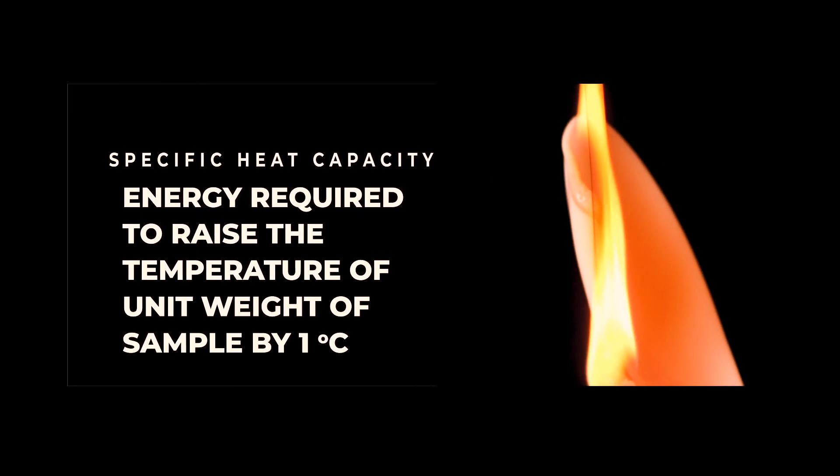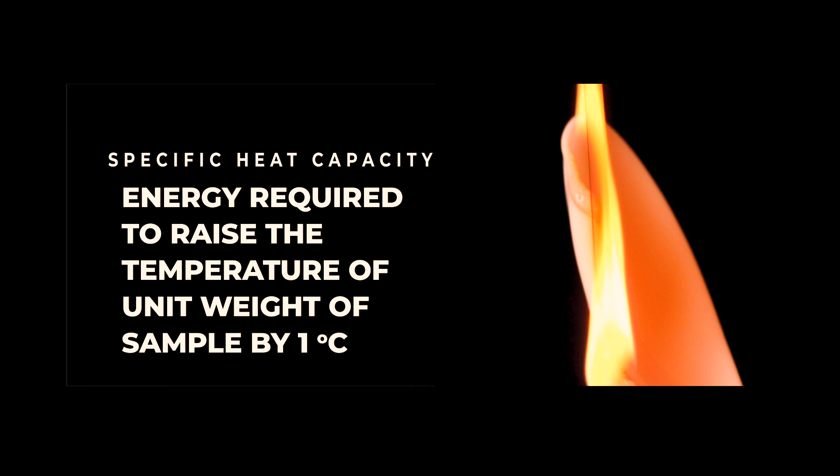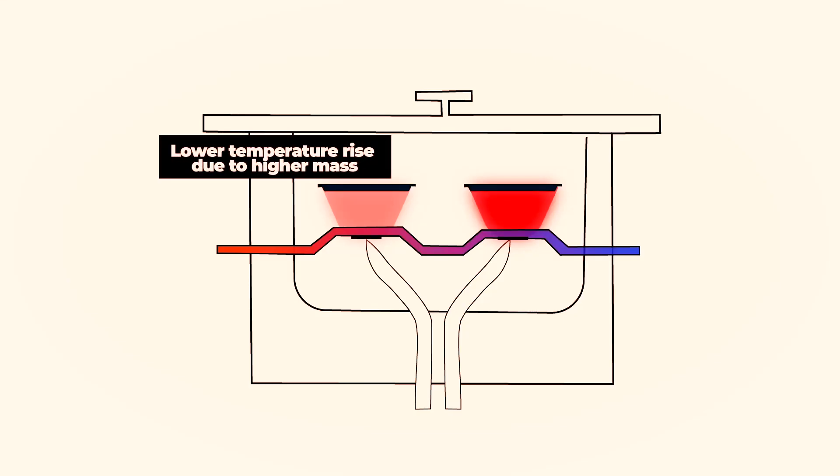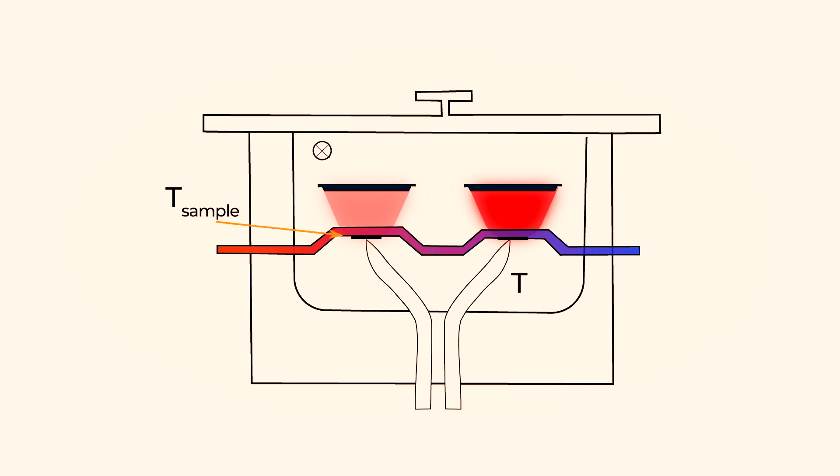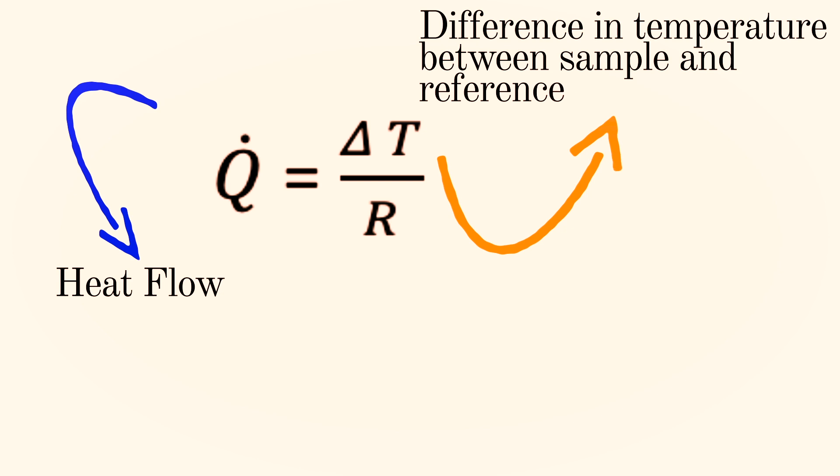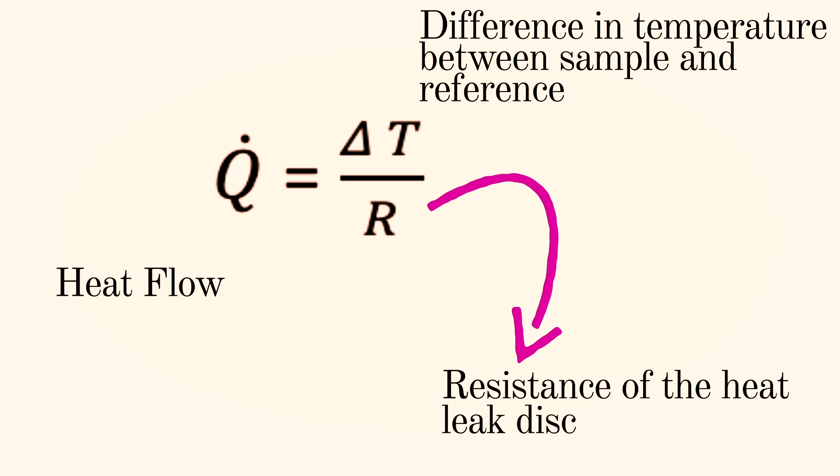Specific heat capacity is the heat absorbed by a unit weight of the sample as it moves through 1 degree C increase in temperature, which is why more heat is required to raise the temperature of a heavier sample. The temperature of the sample block and the reference are measured by the thermocouples. Heat flow is calculated based on the thermal equivalent of Ohm's law as shown in this equation. Where q dot is the heat flow, delta T is the difference in temperature between the sample and the reference, and R is the thermal resistance of the heat leak disk.